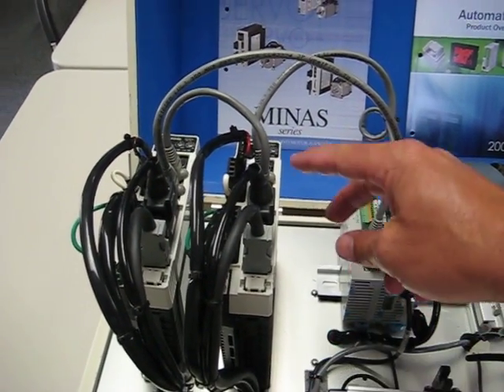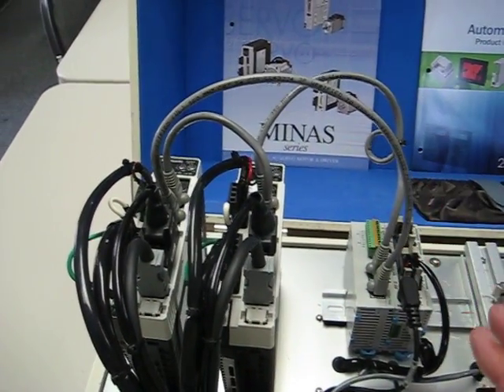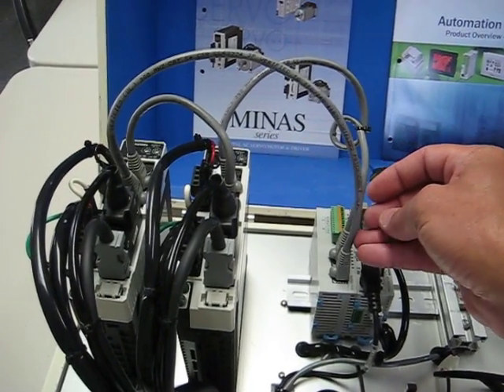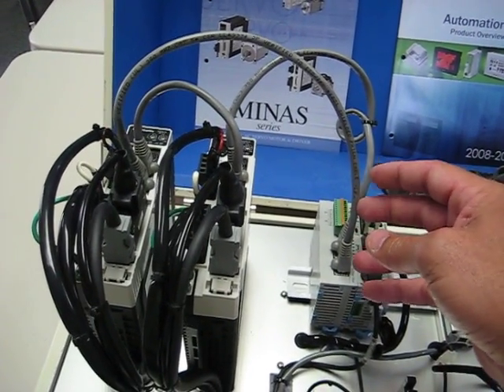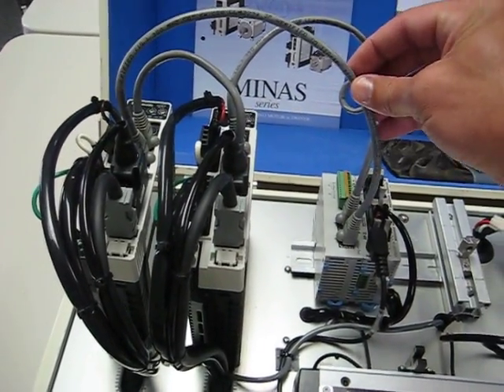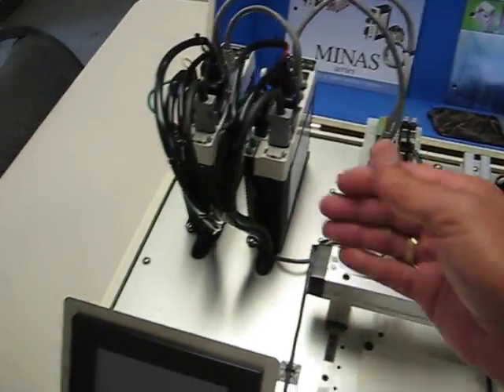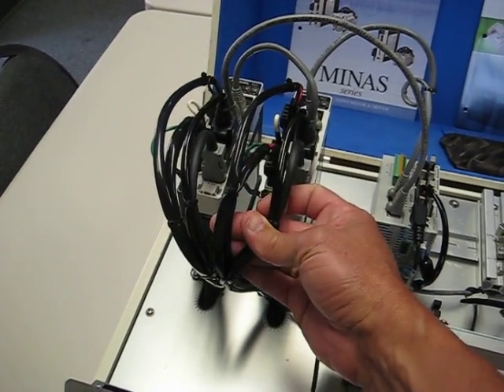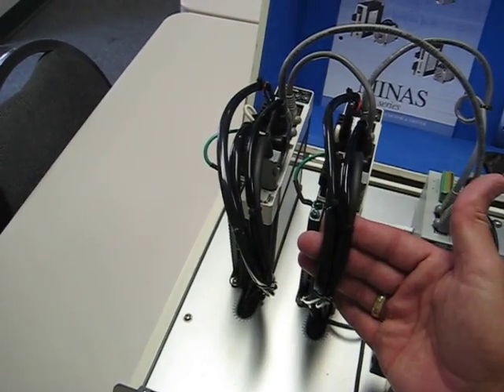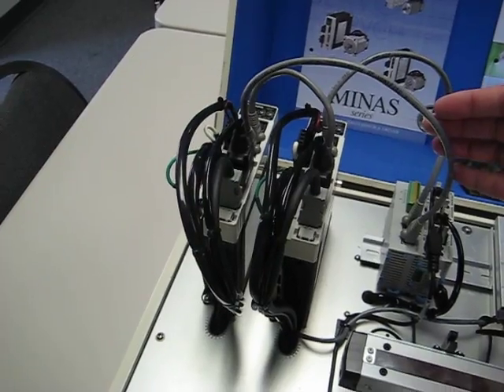These runs of cable from node to node can be up to 200 feet each, and they also communicate at 100 megabits per second — a very fast level of communication to get data to and from the amplifiers. By having Cat5 cables, which are inexpensive, it allows you to mount the amplifiers out in the field closer to the motors. That lets you keep the more expensive power cables and encoder feedback cables very short, which is a way to dramatically reduce the cost of your system.